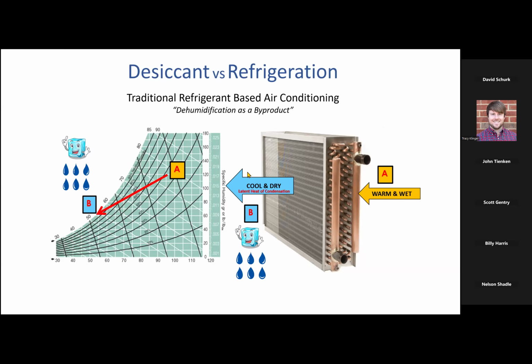Now, what we see here is what I like to call, and this is long-winded, so bear with me, a traditional refrigerant-based cold surface air conditioning system that dehumidifies the air as a byproduct of its temperature. Oh man, that was a lot to say, but I'm going to unpack that here for you in a minute. On the right-hand side, we see a traditional cooling coil. It's made of copper tubes and aluminum fins through which I will pump some type of a cold fluid or refrigerant. It might be direct expansion, R410A or whatever. It might be chilled water, right?